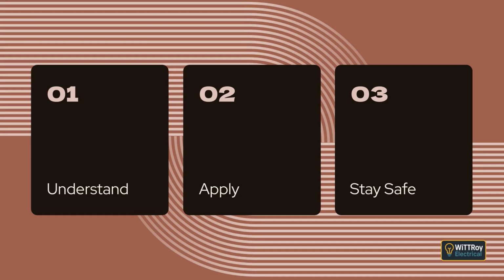Clause 7.5.8 Control of an electrical installation. Clause 7.5.8.1 Main switches. This clause explains that the supply to an extra low voltage installation must be controlled by a main switch or switches operating in all unearthed conductors. An exception explains that this requirement does not apply when the extra low voltage installation is supplied from part of a higher voltage installation where the extra low voltage depends on the higher voltage supply and the high voltage main switch disconnects both systems.